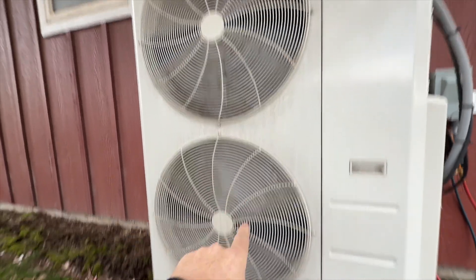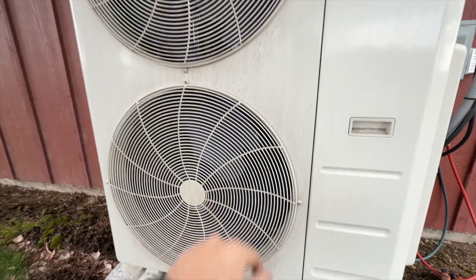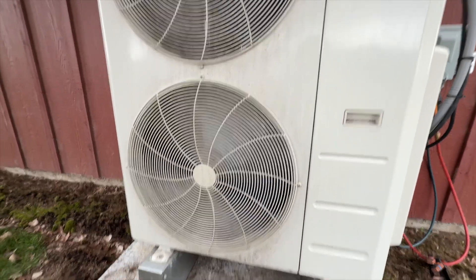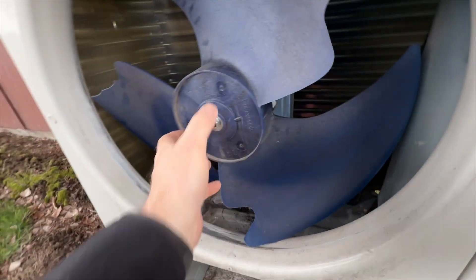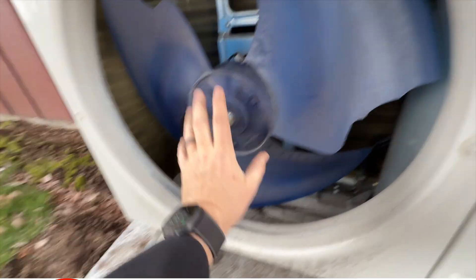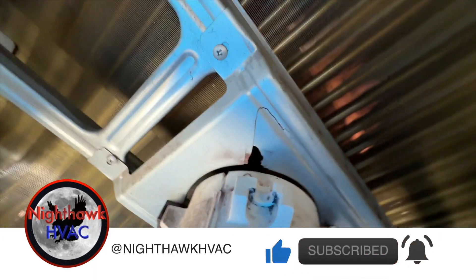So when I got here, I noticed the top one was spinning but the bottom one isn't. Let's see if we can spin it — maybe there's something stuck in there. We got her opened up and the first thing I noticed is this is broken. It's rubbing up on here, and that's because this is all loose. Look at that — the bracket broke.